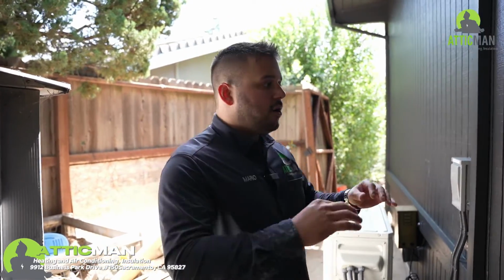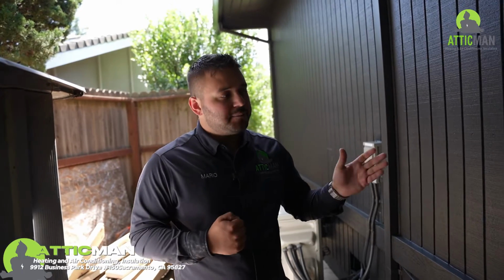The other reason is we talked about earlier BTUs on a mini split system, right? Let's say, for example, you have 3 heads and they are 9,000 BTUs each, which is a common size for a bedroom for a mini split system. You add all 3 of those up, that means you have a total of 27,000 BTUs. If you're just running 1 head, you're only using 9,000 BTUs, that's fine, but all 3 of those heads connect to the same outdoor unit. So you have to go for worst case scenario, right? Worst case scenario, it's a hot summer day, all 3 heads are running on full blast. That outdoor unit needs to be able to handle that demand, right? And it's very simple. You add up the BTUs. In that example, 3 9K heads gives us 27,000 BTUs, right? Outdoor unit needs to match that. We need to make sure we have at least 27,000, if not more, BTUs on the outdoor unit in case all 3 of them are calling for the same time.